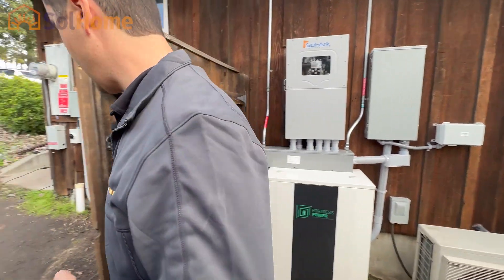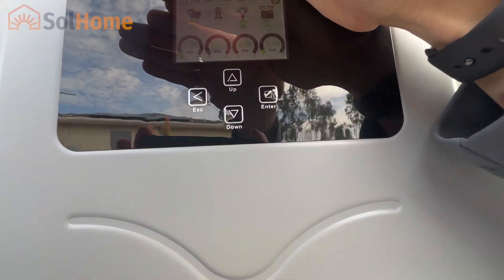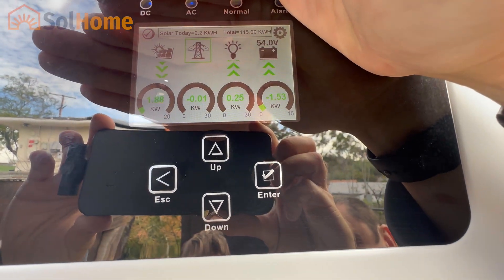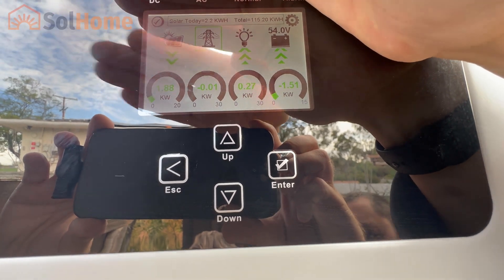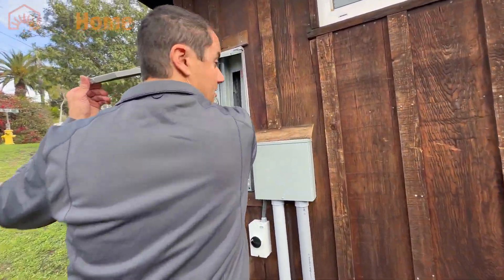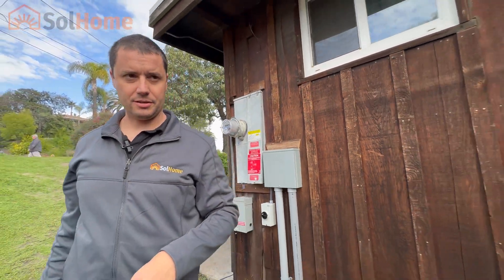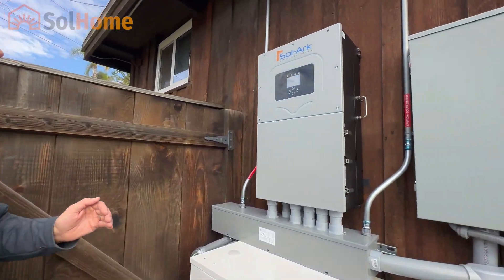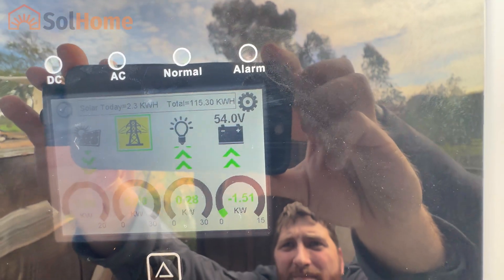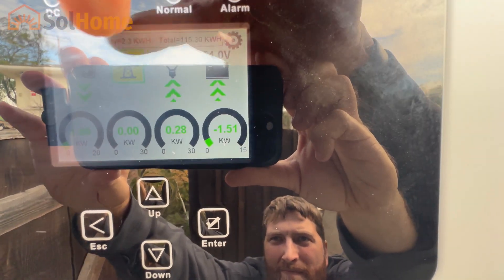Let's do a grid-down test. Right now on the display you can see the grid reading. I'm going to go ahead and hit this breaker and turn this off. Okay — let's go back and check out the inverter. So now there is no grid power — let's see if the Sol-Ark did its thing. As you can see, the grid is down, no longer connected, but the house is still on. Batteries are still charging because we still have solar. Brilliant — it could go like this as long as the sun is shining. Very impressive system.